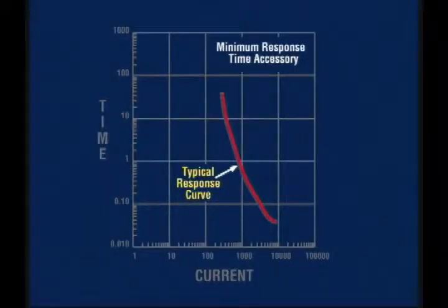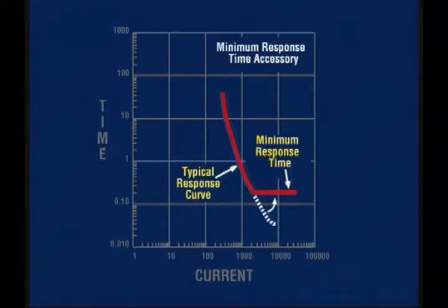The minimum response time accessory achieves coordination between inline protective interrupting devices where fault currents could cause simultaneous tripping. The accessory inhibits tripping until a predetermined minimum time has elapsed. Let's say, for example, that the minimum response time selected is 0.145 seconds. When current above the minimum trip level is detected, the accessory activates, modifying the TCC minimum response time to 0.145 seconds.